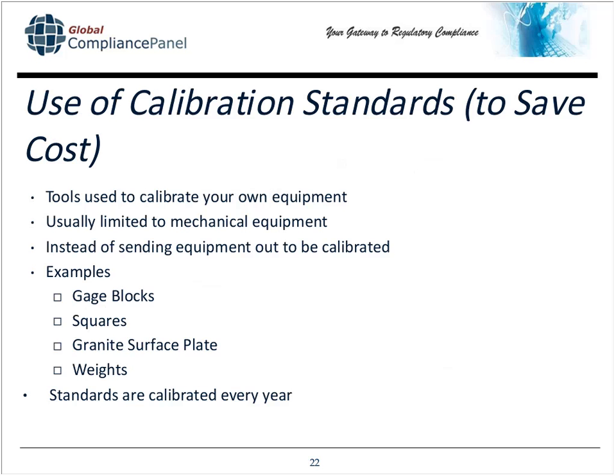When you use calibration standards, they absolutely save cost. There are some limitations, though. You're going to use it to calibrate your own equipment. It's usually limited to mechanical equipment as opposed to electronic equipment. Most companies in the medical device or pharma industry lack the expertise to use external calibration standards to calibrate things electronically. And if you're within that limitation, you don't have to send equipment out to be calibrated. You send your standards out, but you're going to continue to use your in-house test measurement equipment in the meantime.